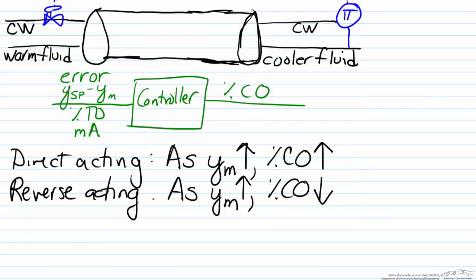By convention the gain for a direct acting controller is less than zero, and the gain for a reverse acting controller is greater than zero, which at first glance seems a bit counterintuitive. These signs are solely an issue of sign convention, most notably the sign convention that we give valves. Recall that fail closed valves take a positive sign and fail open valves take a negative sign, which is relatively arbitrary. The reason why those signs were selected is because fail closed valves tend to be more commonplace in chemical processes.